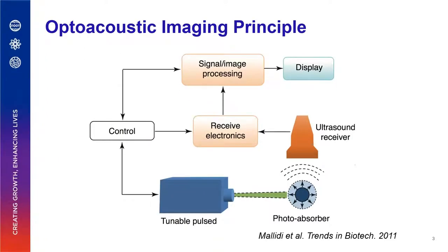Here's a quick overview of the optoacoustic imaging principle. The word optoacoustic literally means light and sound, or more specifically, light-induced ultrasound. Tissue absorbs light from the laser that is impinging on it, and that causes a thermoelastic expansion of tissue, which in turn generates an ultrasound wave. The wave can then be detected by a conventional ultrasound transducer that converts the waves to electrical signal, which can then be processed using signal imaging processing algorithms to form an image. A typical optoacoustic setup consists of a tunable nanosecond pulse laser source as well as an ultrasound detection system.